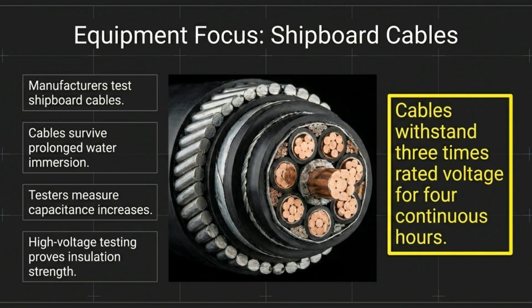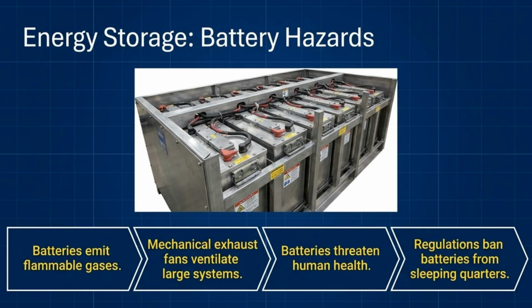Shipboard cables are built tough. Manufacturers test them to survive water immersion and ensure they can withstand 3 times their rated voltage for extended periods. Energy storage, like large battery banks, presents unique hazards. Due to the emission of flammable gases, strict ventilation requirements are enforced, and batteries are strictly prohibited in sleeping quarters.